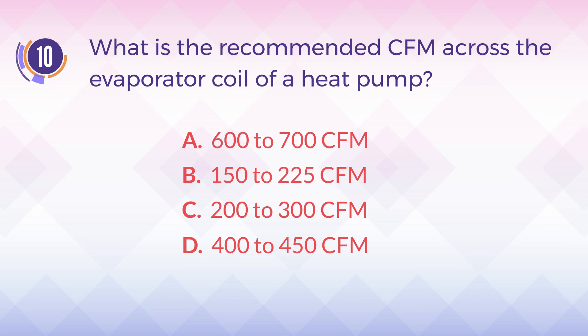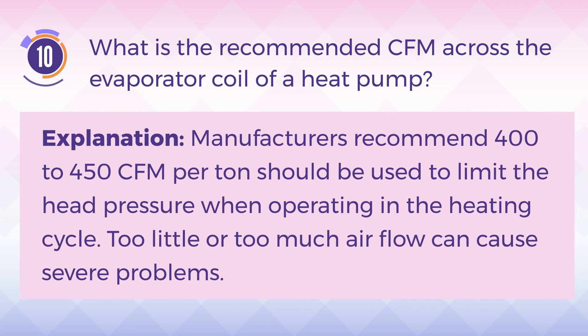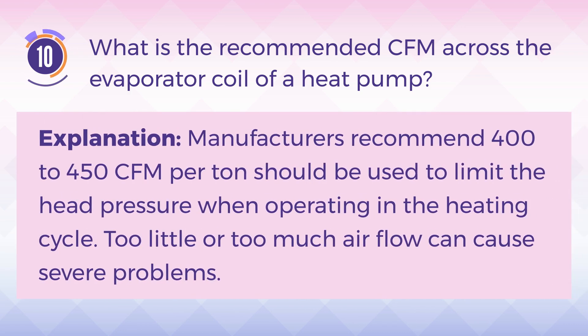The answer is D, 400-450 CFM. Explanation: Manufacturers recommend 400-450 CFM per ton should be used to limit the head pressure when operating in the heating cycle. Too little or too much airflow can cause severe problems.